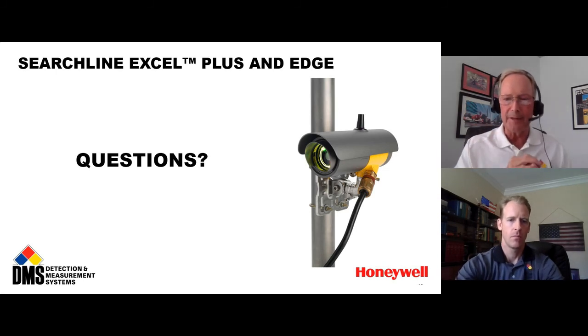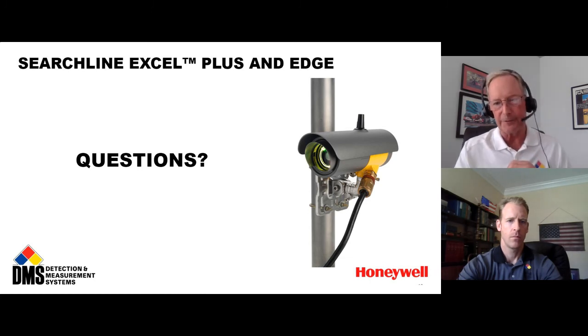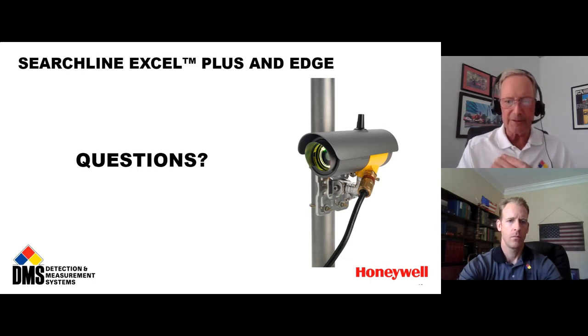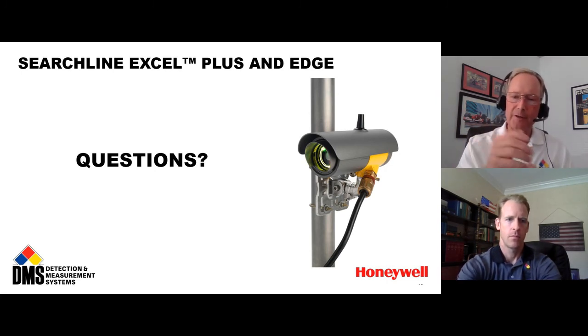You click the next button, and there are two test filters: a low test filter and a high test filter. So you push the next button, and then a screen appears saying to take the low filter and insert it into the IR receiver. You insert it into the IR receiver, and after about 3 seconds, the screen on your Bluetooth display will transition to stating test completed and passed, and it'll say remove low test filter.